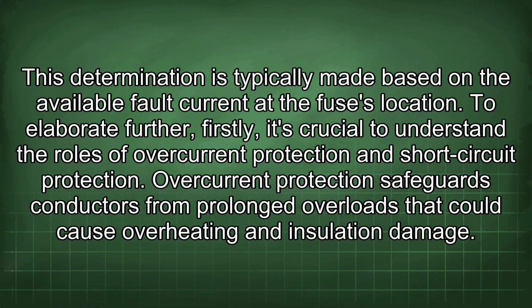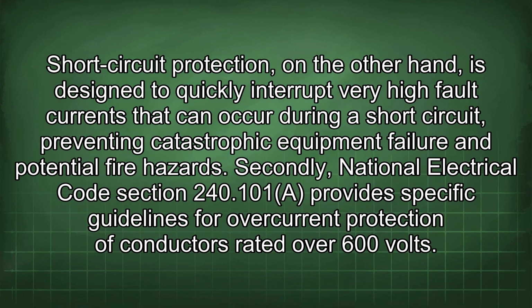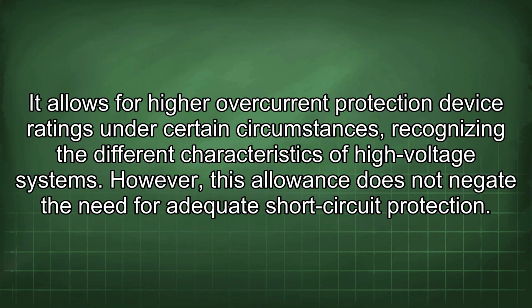To elaborate further, firstly, it's crucial to understand the roles of overcurrent protection and short-circuit protection. Overcurrent protection safeguards conductors from prolonged overloads that could cause overheating and insulation damage. Short-circuit protection, on the other hand, is designed to quickly interrupt very high fault currents that could occur during a short circuit, preventing catastrophic equipment failure and potential fire hazards. Secondly, National Electrical Code Section 240.101 provides specific guidelines for overcurrent protection of conductors rated over 600 volts. It allows for higher overcurrent protection device ratings under certain circumstances, recognizing the different characteristics of high-voltage systems. However, this allowance does not negate the need for adequate short-circuit protection.